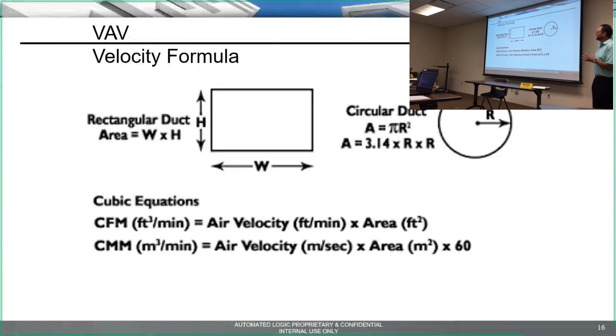So knowing that, now I know the velocity. I've got 2,000 feet per minute coming into the inlet of the VAV box, and now I need to know the duct size. If I know the velocity and I know the duct size, I can calculate the CFM. How many cubic feet per minute are going to the space? It's just a simple formula. You take the air velocity, which is 2,000 feet per minute, times the area, and you end up with cubic feet per minute. Make sense? That's just finding the area of a square or the area of a circle, measuring the velocity pressure, calculating the feet per minute, and multiplying the feet per minute times the area to get your cubic feet per minute. That's how the VAV controllers in that building measure the airflow.